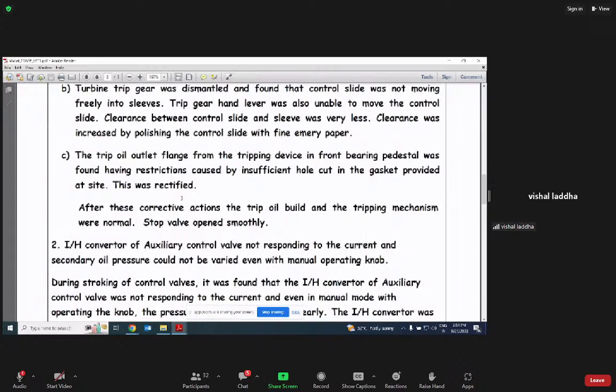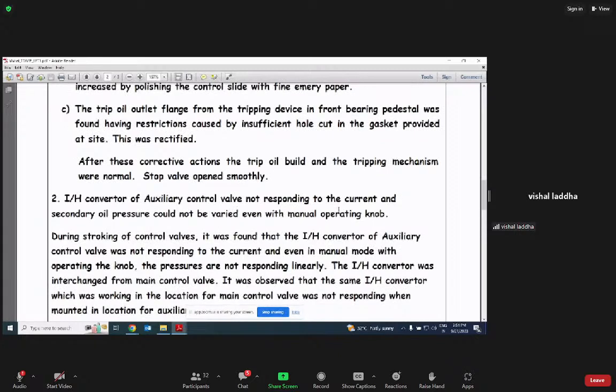The trip oil outlet flange from the tripping device in front of the bearing pedestal was found having restriction caused by an insufficient hole cut in the gasket provided at site. After all these corrective actions, the trip oil build up and the tripping mechanism were normal. The stop valve opened smoothly. Now the I/H converter of the auxiliary valve, the second problem. What was the second problem?